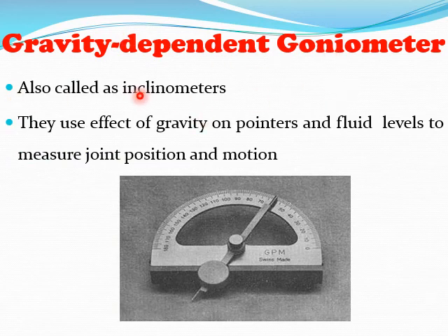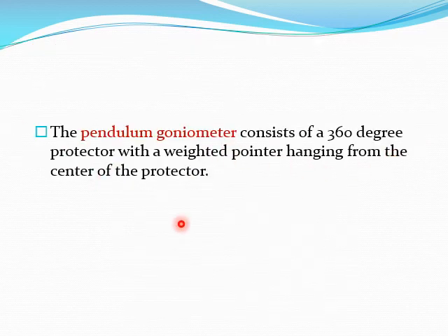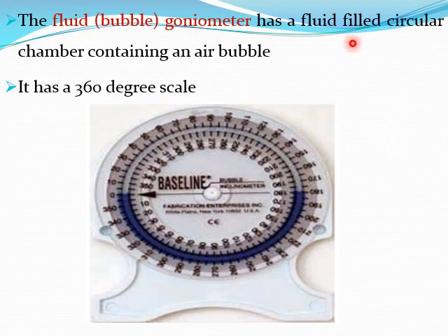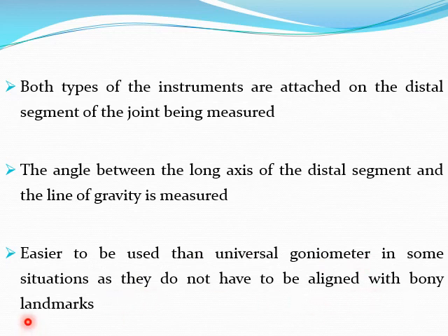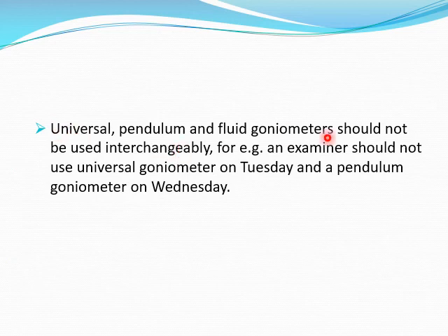The gravity-dependent goniometer, also known as the inclinometer, uses the effect of gravity on pointers and fluid levels to measure joint position and motion. The pendulum goniometer consists of a 360-degree protractor with a weighted pointer hanging from the center. The fluid goniometer has a fluid-filled circular chamber containing an air bubble, with a 360-degree scale. The instrument is attached on the distal segment of the joint being measured. It is easier to use than the universal goniometer in some situations as it does not need to be aligned with bony landmarks. Universal, pendulum, and fluid goniometers should not be used interchangeably.